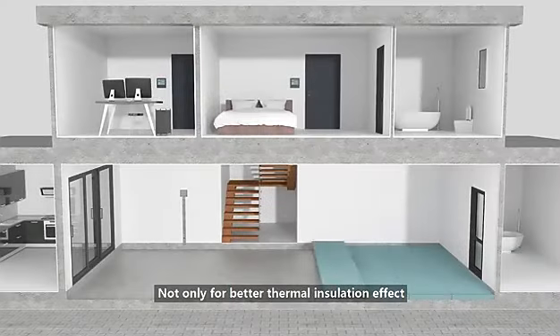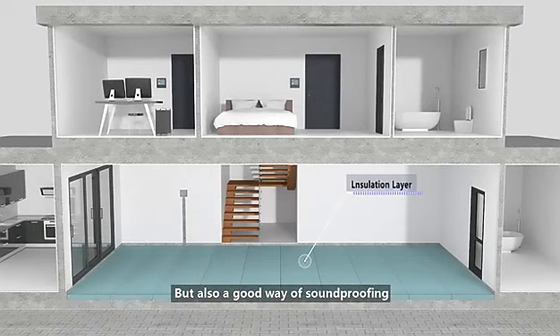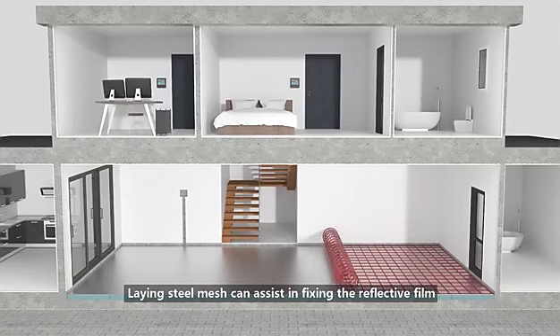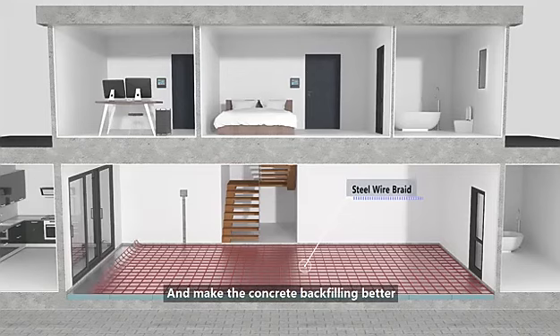Lay insulation layers — not only for better thermal insulation effect, but also a good way of soundproofing. Lay aluminum foil reflective film to make the heat conduction of the floor heating cables faster and more even. Laying steel mesh can assist in fixing the reflective film as well as the floor heating cable, and make the concrete backfilling better.